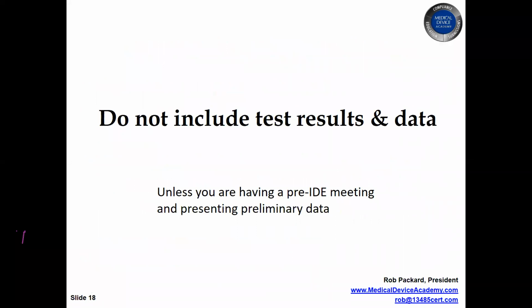The FDA asks you not to include test results and data. If you have already done the test, why are you asking questions about what testing you should do? Now, if we're having a pre-IDE meeting, and that's the purpose of the pre-sub, then you probably want to have some preliminary animal data. You might even have a first-in-human study, and that's what you're presenting to the FDA to get their feedback before you go ahead and design your final clinical study design for the pivotal study. That would make some sense.